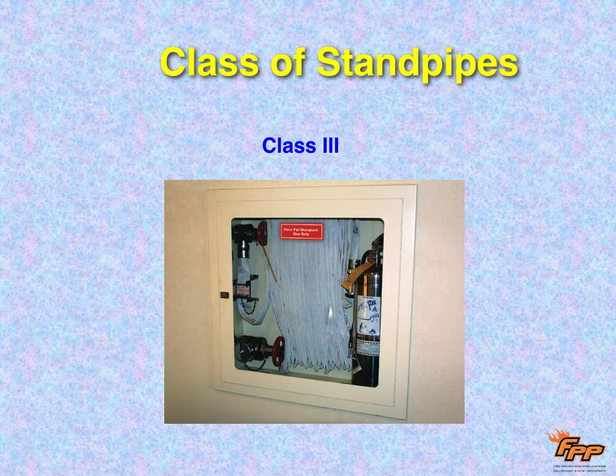So class one is for firefighters because firefighters are first class. Class two is for you, the public, okay? Class three is for you and me. It's for the public and for the firefighter. So class three, if you look at this picture in the top left, that is the connection for the fire hose that's for public usage, that's connected to a nozzle. It's going to be at a much lower gallons per minute and a much lower pressure, but it will work for the public if they grab it.